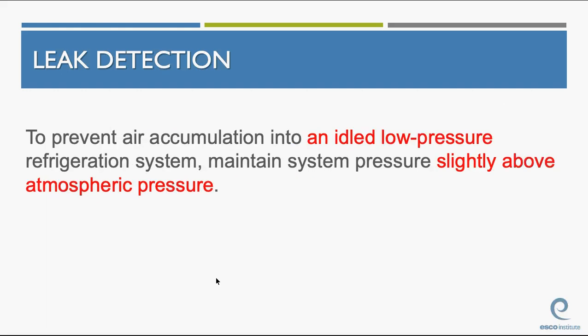To prevent air accumulation into an idle low-pressure system, in other words, if I've mothballed it, if I've shut it down for a while, I can add pressure to it to bring it slightly above atmospheric pressure. Not over 10 psi above, but slightly above atmospheric pressure. What that allows me to do is make sure I'm not pulling moisture into a system, because moisture in a refrigeration system is bad.